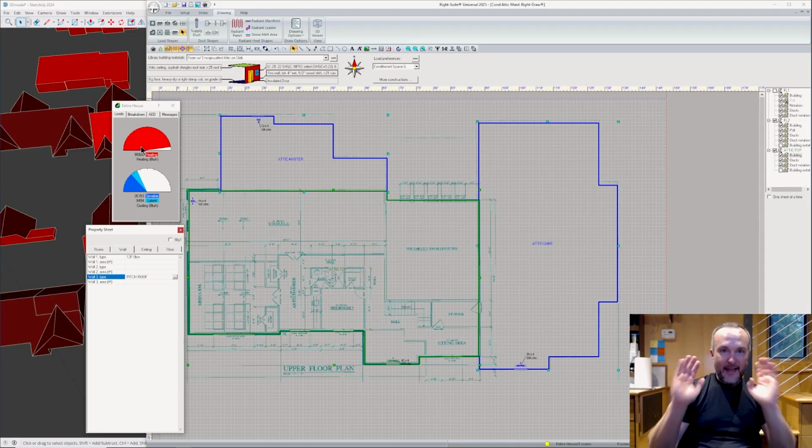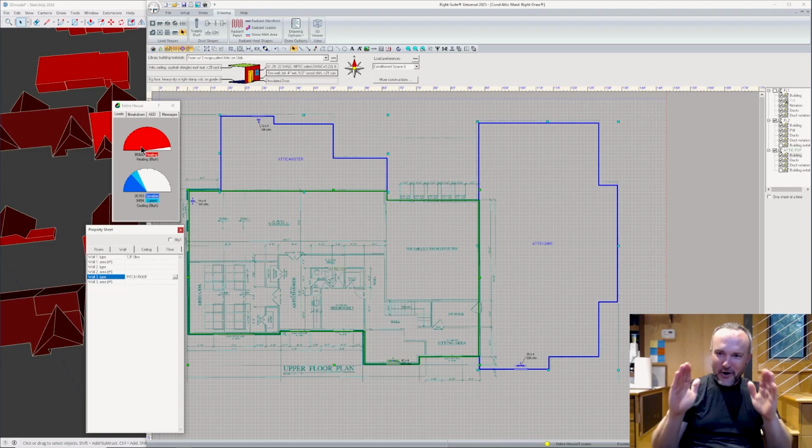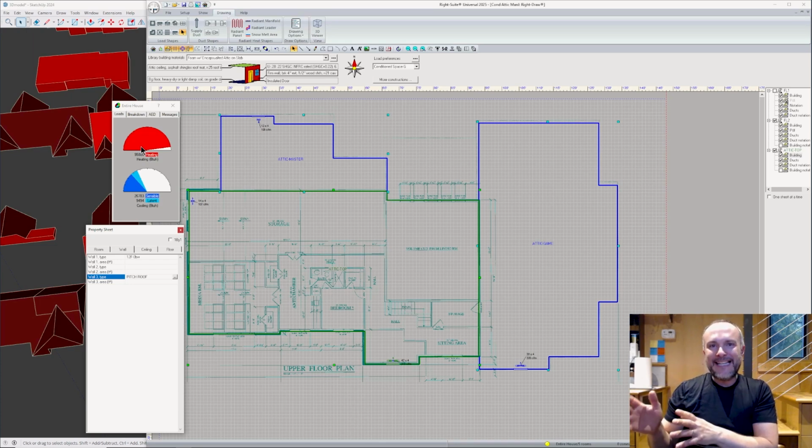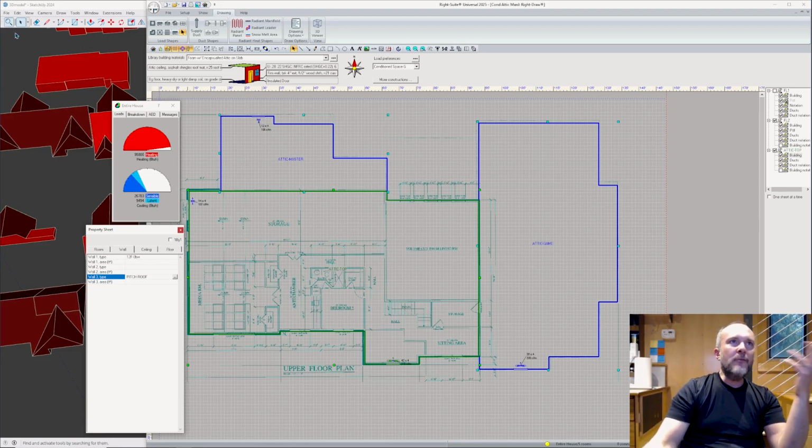That being said, if you get somebody who just believes in math alone in America today, that's an achievement. So go with that, knowing that it's not just a math and a science, but it's also an art, because the assumptions built into that red number up there are wrong themselves. You're not going to find that anywhere in the reports. That's another thing that they're trying to solve in this rewrite of Manual J right now. You're allowed to oversize heat pumps by up to 15,000 BTUs per hour capacity to try and hit that heating, but obviously we can't do that here. You're going to think that you need to install a furnace AC combo, which is totally not true.